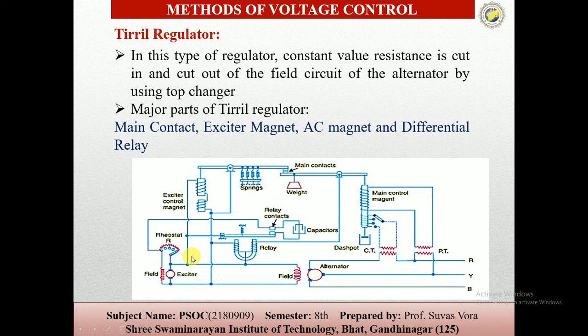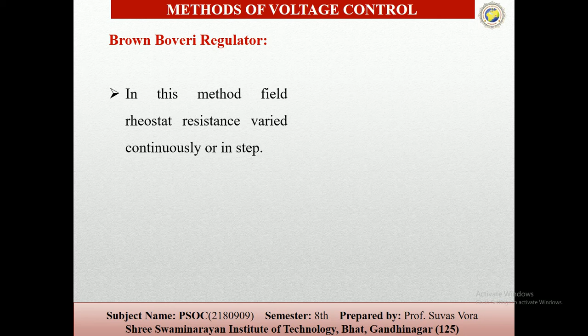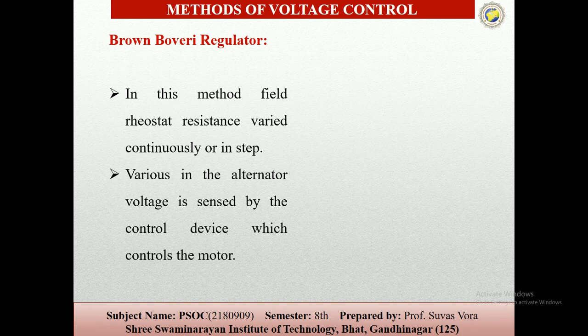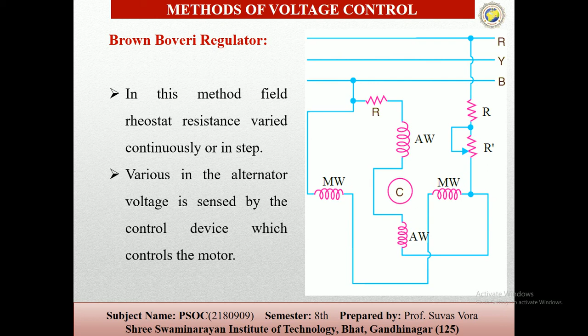So these are the Brown-Boveri regulators. So in this method the field rheostat resistance varies continuously and step by step, and the variation in the alternator voltage is sensed by the control device which controls the motors. So this construction consists of two windings, one is the main winding which is represented by MW, and another one is the auxiliary winding which is represented by AW, and the auxiliary winding is divided into two equal parts. So these are the Brown-Boveri regulator systems.